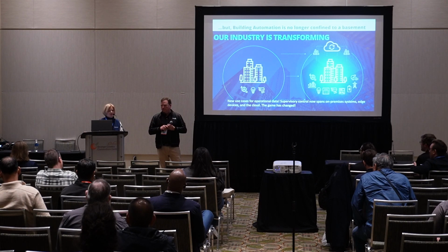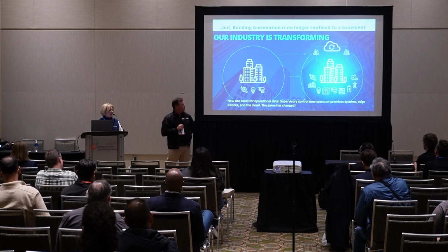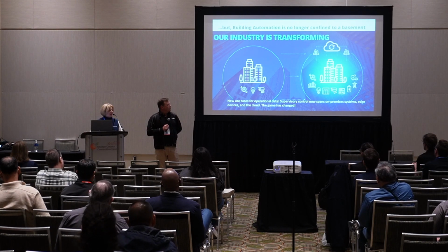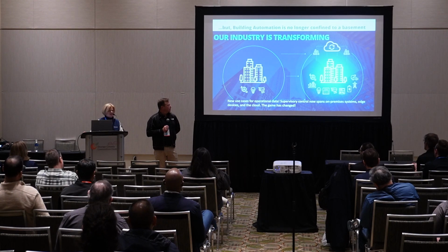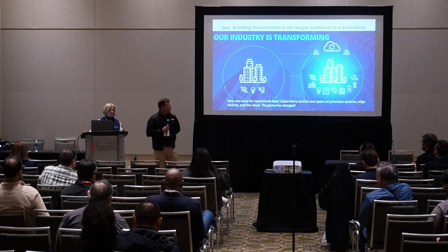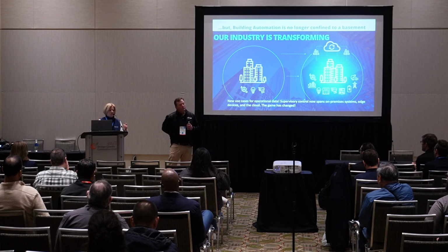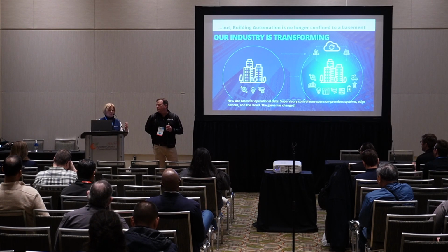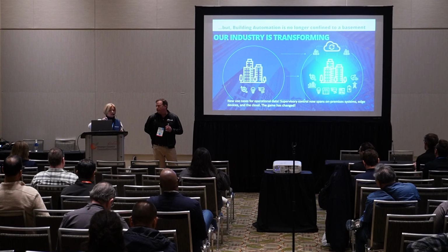I think the buzzwords are moving much faster than the industry. But I love the little elevator icon down there. If you were on the right side of the diagram, you might want to trend your data and sample what's typical every 20 minutes. But how much data do you really want to store? Even if you're moving things up to the cloud, you don't want to use every single point just because there are points. You really want to think about how much data you're moving around and that sampling rate.